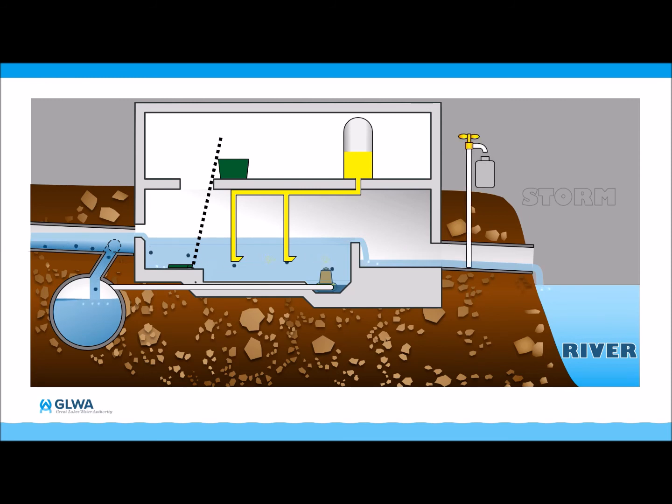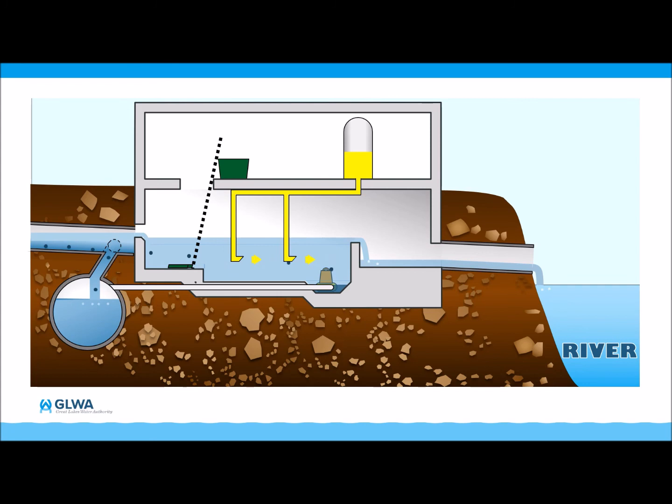We also collect samples of the CSO leaving the basin and analyze the types and amounts of pollutants being discharged. We also test for fecal coliform bacteria, microorganisms that indicate the presence of pathogens, to verify that we have sufficiently disinfected the water to meet the quality standards set by the Michigan Department of Environment, Great Lakes and Energy or EGLE.